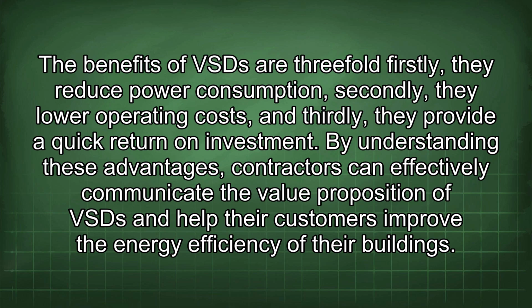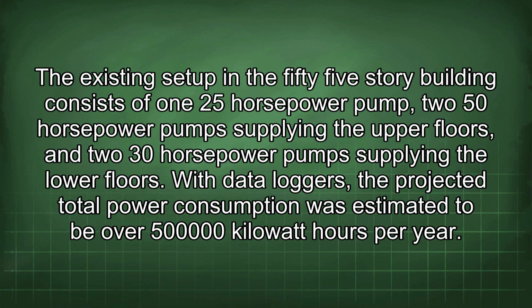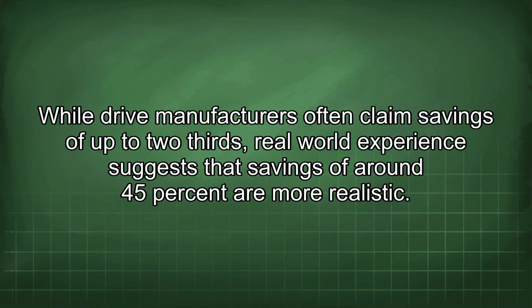efficiency of their buildings. The existing setup in the 55-story building consists of one 25-horsepower pump, two 50-horsepower pumps supplying the upper floors, and two 30-horsepower pumps supplying the lower floors. With data loggers, the projected total power consumption was estimated to be over 500,000 kilowatt-hours per year.